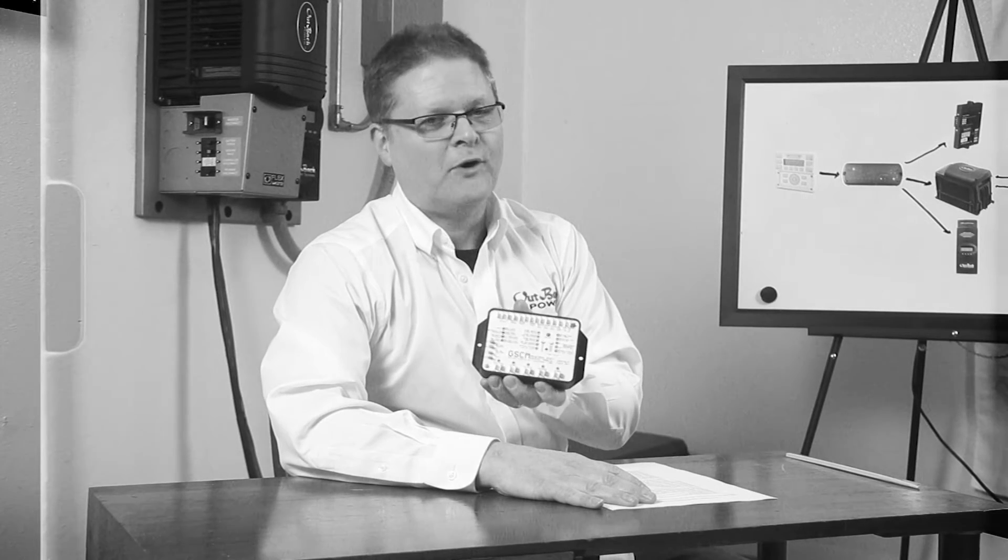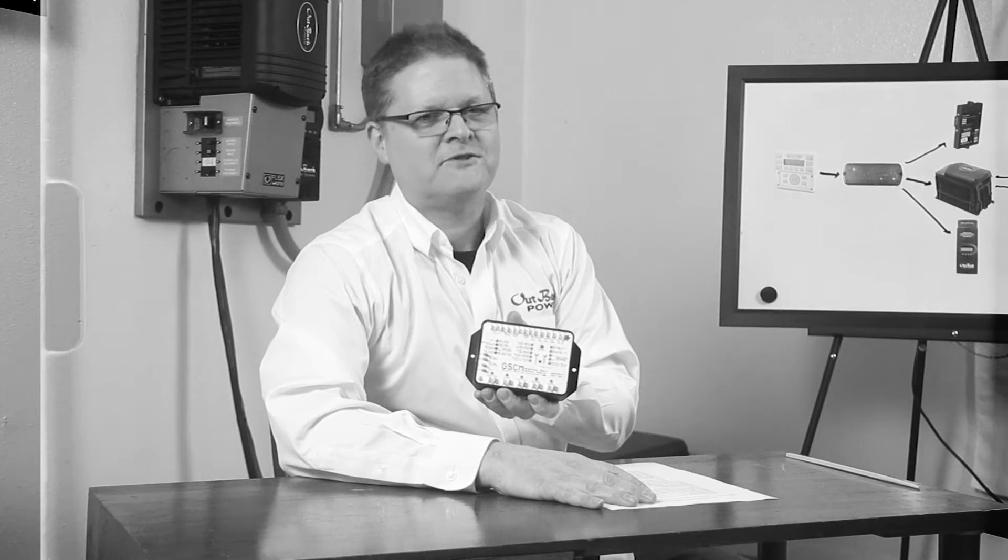Although AGS was designed to work with a two-wire start generator, you may use a generator start control module or GSCM to convert a three-wire start gen to a two-wire. Here's one made by Atkinson. More info under the description.